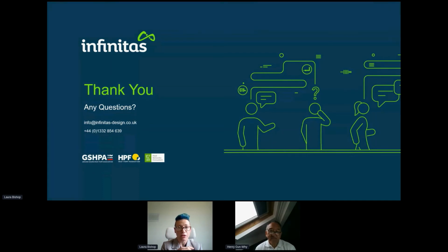You will have to contact the DNO. If you're doing a feasibility study on a heat pump, that's one of the things you have to bear in mind—contacting the DNO as soon as possible, because you might find you're grid constrained in that particular area, and therefore you can't have a heat pump, or you might have to spend £250,000 on an electrical upgrade. That's something the ENA are very aware of, and they're working with people like GSHPA to make sure that's not a showstopper for projects.